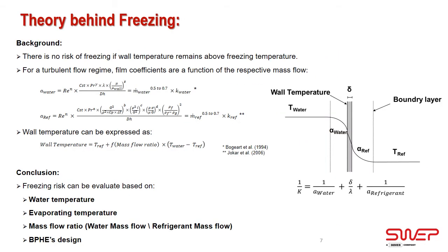First, we will review our freezing project, but before going through all the details, I would like to introduce you to the theory behind it. Let's consider a heat exchanger, any kind of heat exchanger. On one side you have pure water, on the other side of the heat transfer area you have an evaporating temperature of about 35 degrees Fahrenheit. Is there a risk of freezing? For sure, no. But now if we consider a similar case with an evaporating temperature of about 25 degrees Fahrenheit, that makes it a bit more tricky.